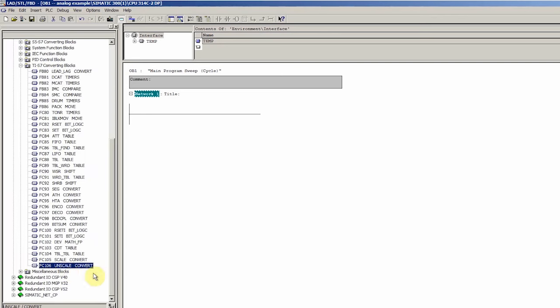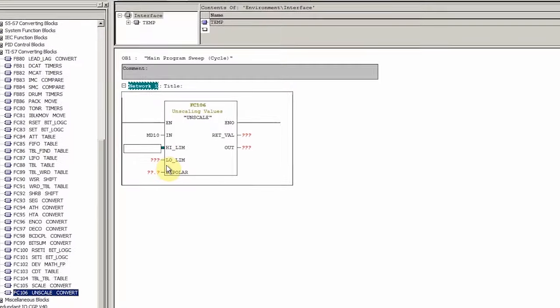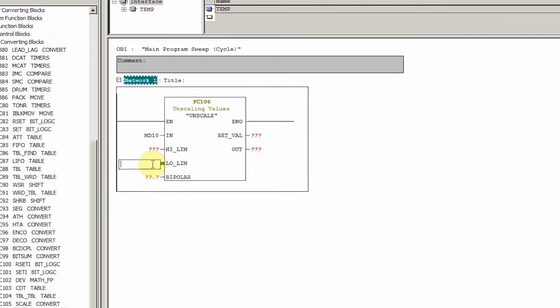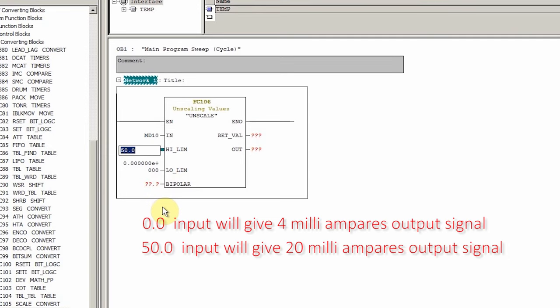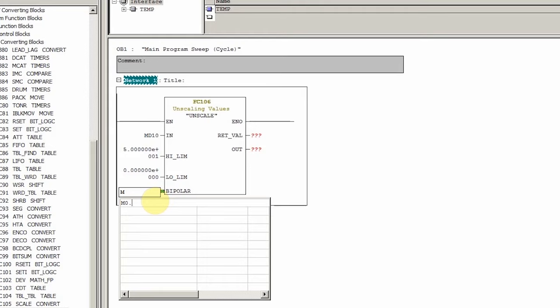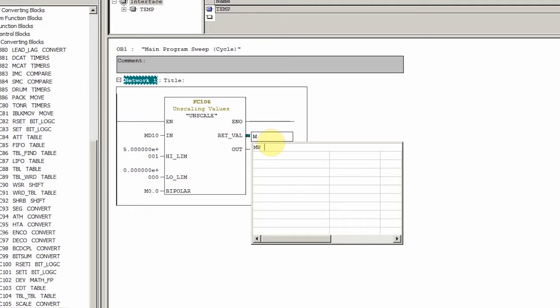Here we will drag and drop the FC106 unscale function. This function is used to generate the analog output signal. We will put MD10 double register as the input of this function — this will be the scaled value for the analog output. Next we will put the low limit as 0.0 and the high limit as 50.0. This will set 0.0 as 4 mA and 50.0 as 20 mA of analog output. Next we can assign a bit to set this scaling block as unipolar or bipolar.